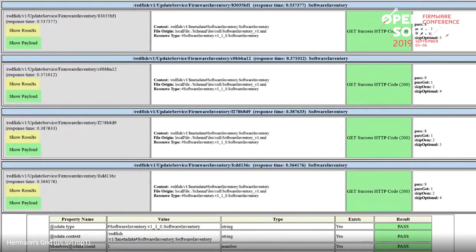This is a Redfish validator run on a recent OpenBMC master build. Our current master in OpenBMC passes with no Redfish validator errors. We run the Redfish service validator in CI against an IBM Power Systems Witherspoon, and at the APTS we were the only implementation of Redfish to pass completely without any Redfish validator errors.